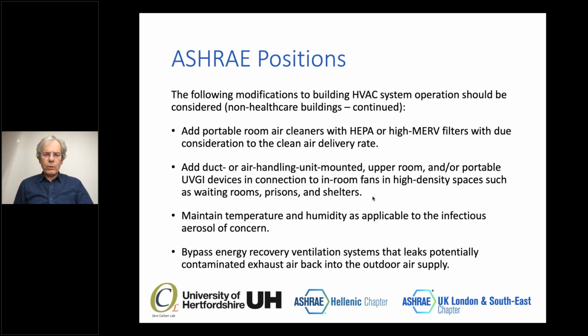Still about modifications of buildings other than healthcare buildings: we need to think about adding portable room air cleaners with HEPA or high MERV filters, with due consideration to the clean air delivery rate. We need to add ducts or air handling unit mounted upper-room and/or portable UVGI devices in connection with in-room fans for high density spaces such as waiting rooms, prisons, shelters, and so on. We need to maintain temperature and humidity as applicable to the infectious aerosol of concern, and bypass energy recovery ventilation systems that leak potentially contaminated exhaust air back into the outdoor air supply.